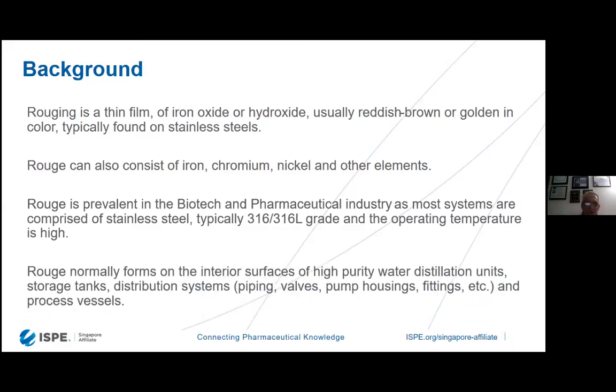Rouge normally forms on the inside of surfaces like distillation units, storage tanks, valving, piping, pump housings, fittings, etc., and in process vessels. And of course, you see it on heat exchangers too. Even though heat exchangers are not part of the actual flow of the water in our system, you see a lot of Rouge on heat exchangers also due to the hot temperatures and the oscillation of temperatures from hot to cold.